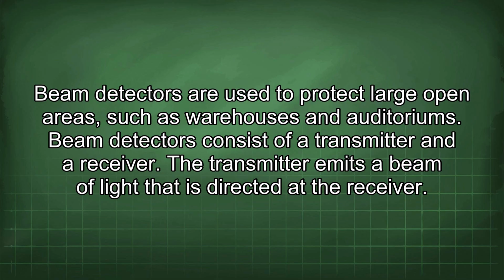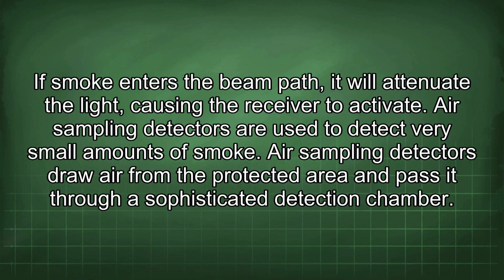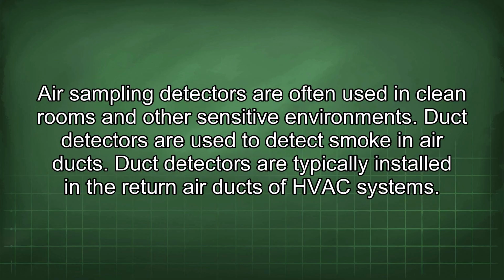Beam detectors consist of a transmitter and a receiver. The transmitter emits a beam of light that is directed at the receiver. If smoke enters the beam path, it will attenuate the light, causing the receiver to activate. Air sampling detectors are used to detect very small amounts of smoke. Air sampling detectors draw air from the protected area and pass it through a sophisticated detection chamber. Air sampling detectors are often used in clean rooms and other sensitive environments.